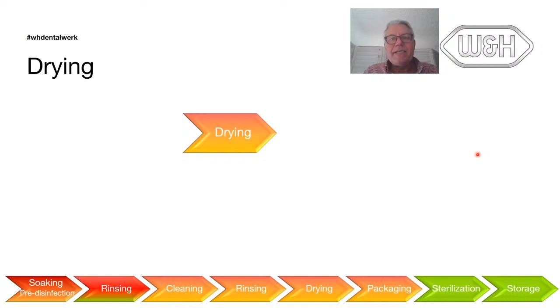For drying, it's nice to use compressed air, because if you realize many of your instruments have hinges, have hollow lumens, which can hardly be dried unless you use filtered compressed air to blow out water. And then you dry the surface with a single-use non-woven tissue.